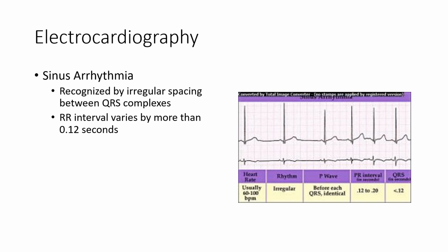If you're imaging a patient and you're gating them, if they have this arrhythmia, then it's going to end up rejecting some beats because it will be hard for that camera to track when to take images. It's going to take a picture either 8 or 16 times between these R to R complexes, but if they're not consistently spaced apart, then it times that, and it could end up rejecting some beats of the heart and only accepting some of the data. This will result in noisy images, especially on SPECT, because it will lead to rejected counts and rejected beats.